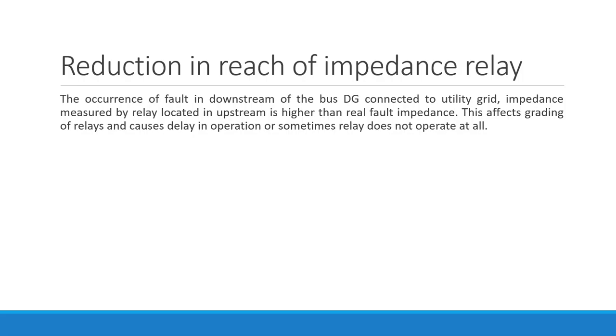Okay. Reduction in reach of impedance relay. When a fault occurs downstream of the bus where a DG is connected to the utility grid, the impedance measured by the relay located upstream is higher than the real fault impedance. So whatever impedance you measure would actually be higher than the real fault impedance. This is going to affect grading of relays and will cause delay in operation, or sometimes possibly the relay is not going to operate. This is happening because the impedance you are measuring is different from what is actually set for the operation of the relay. So this is the problem with the protection of microgrid. I think the things are clear to you.